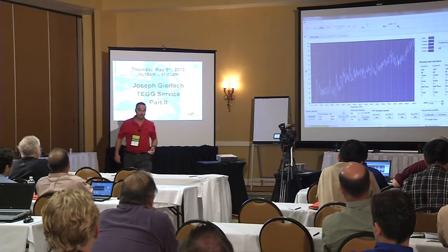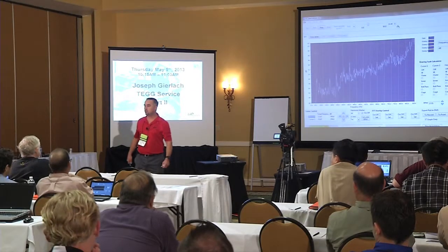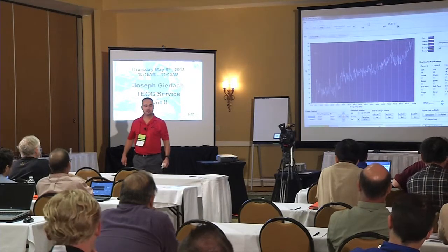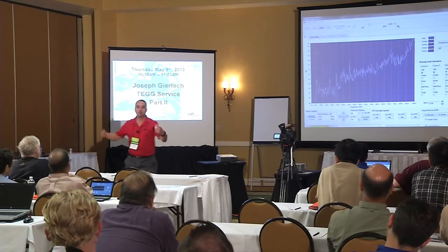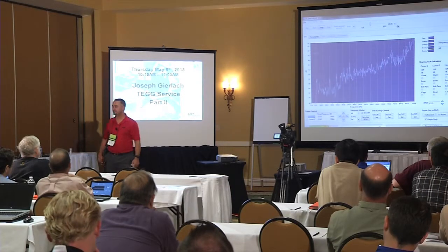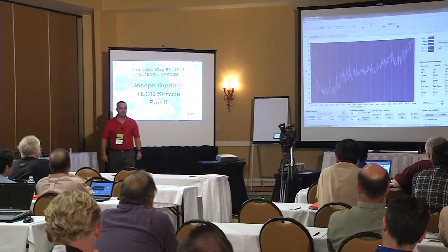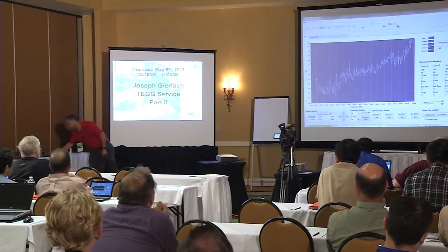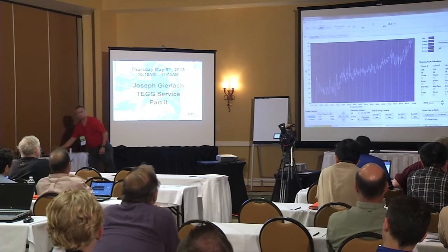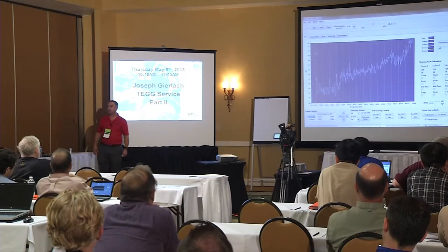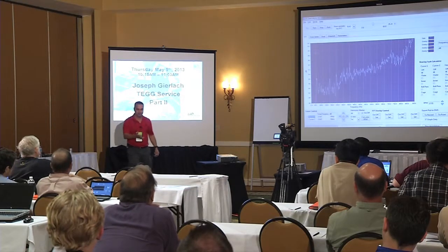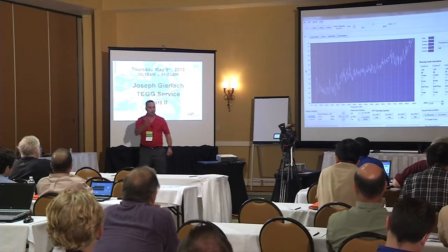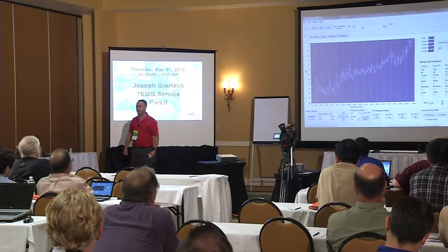Say again? Did anybody analyze this one? What about the tonal quality? Should a 2,000 amp low voltage power circuit breaker sound like this? It sure shouldn't. It should be totally silent. And this has been going on for 2 years. What does the frequency spectrum tell us?